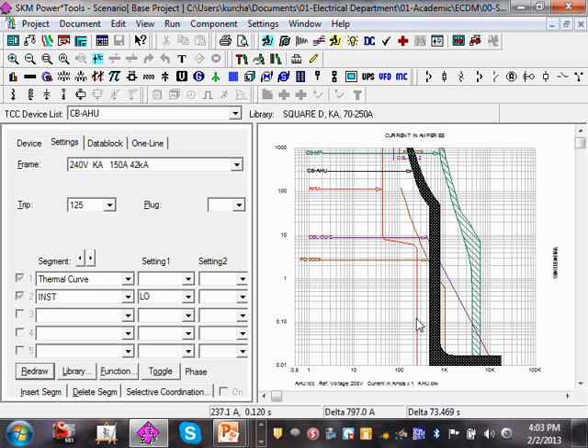Damage curve, continuous amp rating, can run forever, and damage curve rating: the higher the current, the faster the circuit breaker trips, or the higher the current, the faster the conductor is going to melt. Any comments, guys, about this one, the damage curve for conductors?